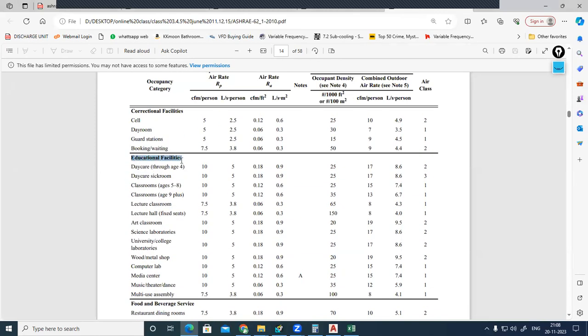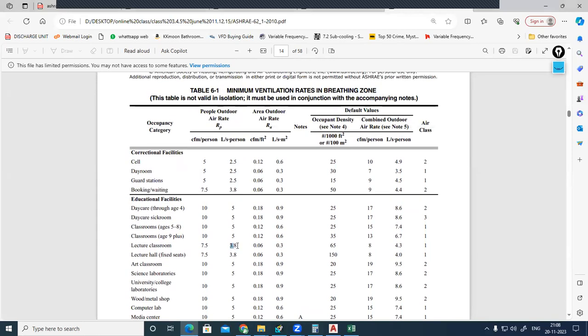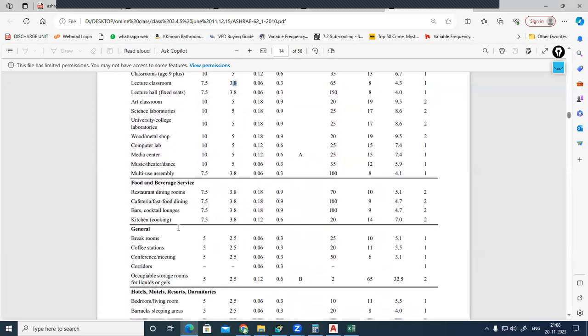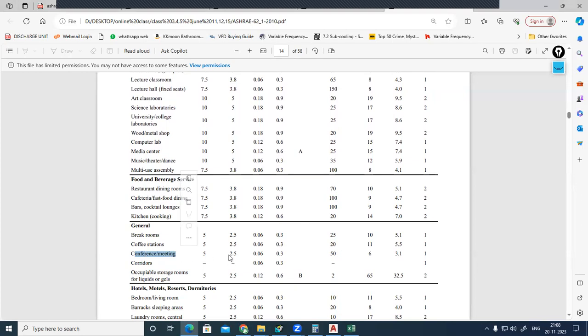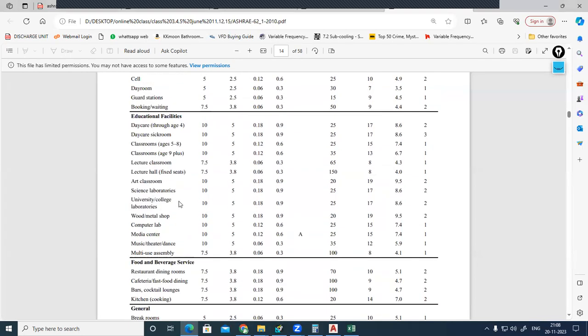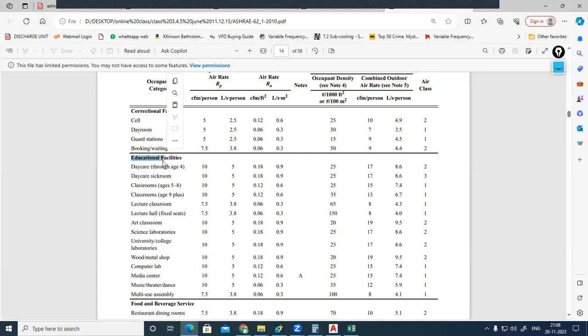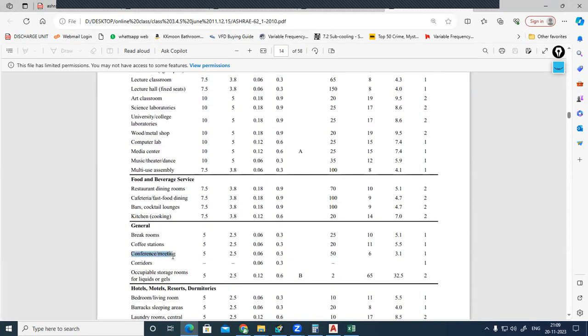But here you can see educational facility. We are having a lecture classroom. And here, each person needs 3.8 liter per second. At the same time, for one person we should deliver 3.8. But for conference or meeting room, we have to introduce 2.5 liter per second only. So it is clear that in education facility, meeting room, lecture or classroom somewhat similar, but the activity level might be slightly different than office. We are dealing with the office, first Abu Dhabi Bank building only. So that's why we are dealing with the office kind of thing. Here you can see the criteria that we need inside the conference room, meeting room, training room, almost the same we can consider.